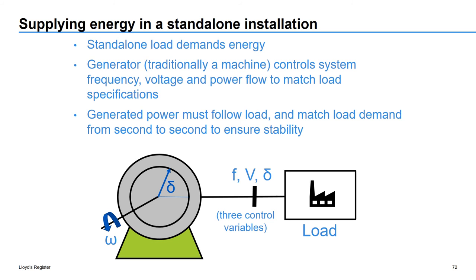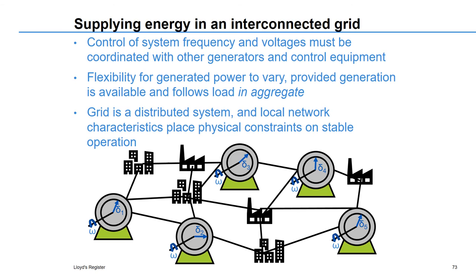And this is generally ensured by the frequency and voltage control that the machines exert on this standalone basis. This is fundamentally different in a grid-connected mode of operation, because now the generator does not have complete control over frequency and voltage at its terminals. These must now be coordinated with all the other plants in the system, and the other plants exert these influences over a distributed network that can impose physical constraints on the operation of any plant and on the power flows that can occur in the network.